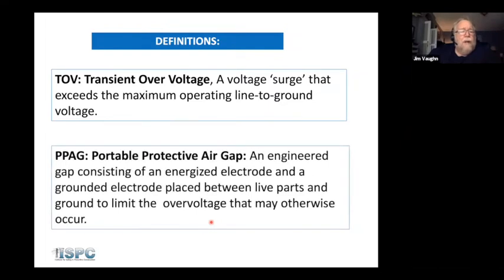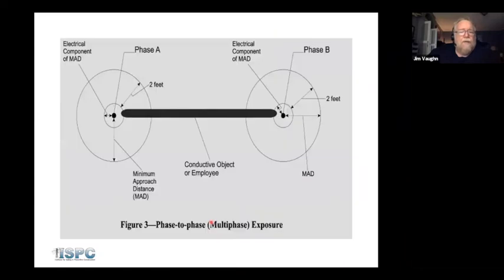You'll hear me mention PPAG in a minute, and when we get to the end of TOV, I'll explain what that is. But this is an engineered gap that's designed with fixed electrodes on the modern equipment that's used to shunt an overvoltage away from the workers who are working an energized circuit in the case of a TOV.